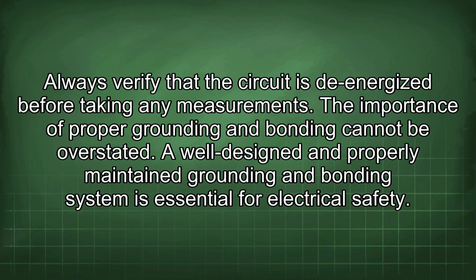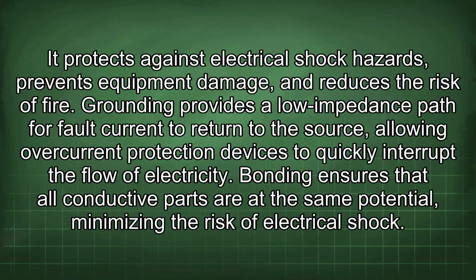The importance of proper grounding and bonding cannot be overstated. A well-designed and properly maintained grounding and bonding system is essential for electrical safety. It protects against electrical shock hazards, prevents equipment damage, and reduces the risk of fire. Grounding provides a low impedance path for fault current to return to the source, allowing overcurrent protection devices to quickly interrupt the flow of electricity.